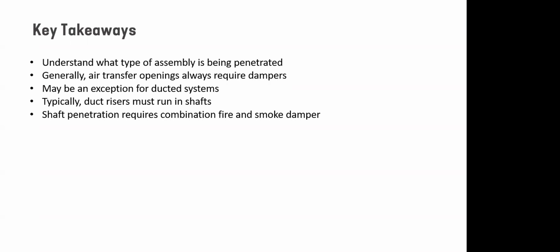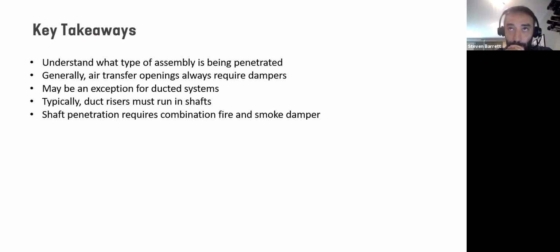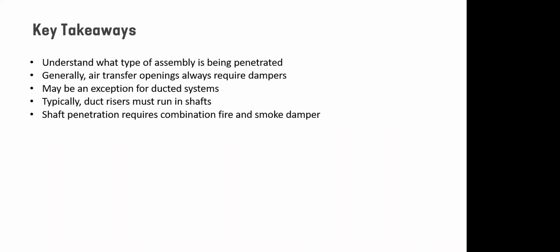So there was a comment in the Q&A about the commentary from the 2015 IMC about what constitutes a ducted HVAC system. So it says, I'll try to read this, it's a little long. It says that a ducted HVAC system in this context does not contain flexible ducts, except where a steel duct passes through a fire barrier and then converts to flexible duct to only serve an air terminal device. In such case, the steel duct could have terminated at an air terminal device on the wall, thus extending the duct run further into the room to a ceiling air terminal device using flex duct has no effect on the integrity of the fire barrier penetration.